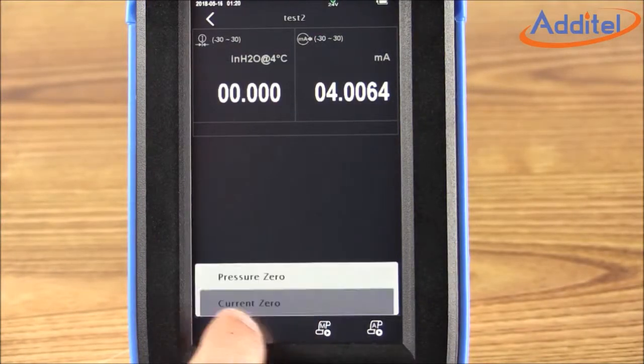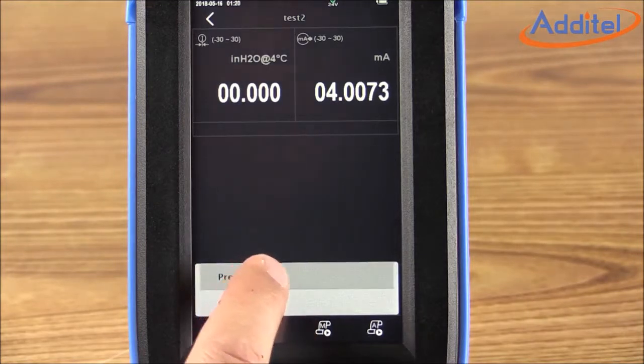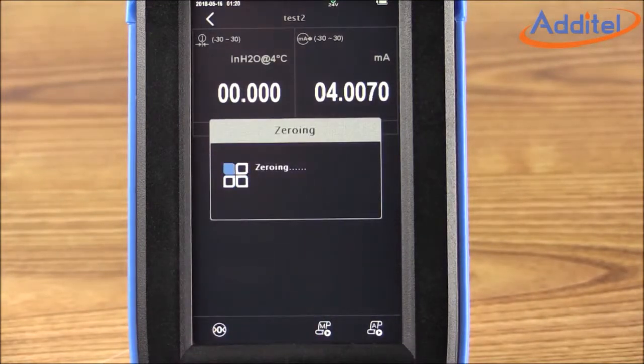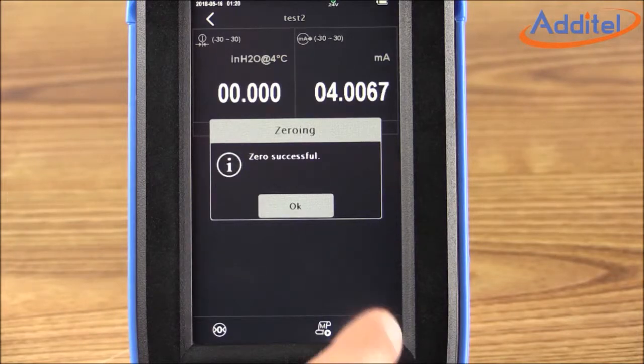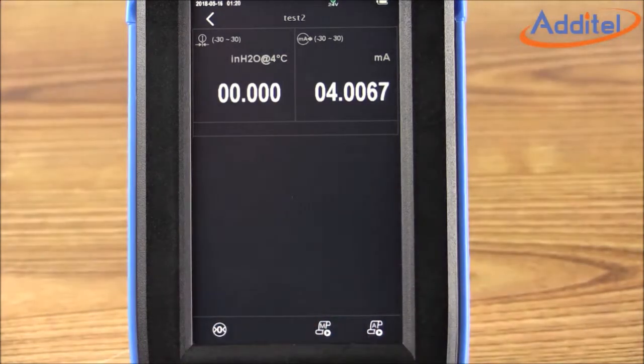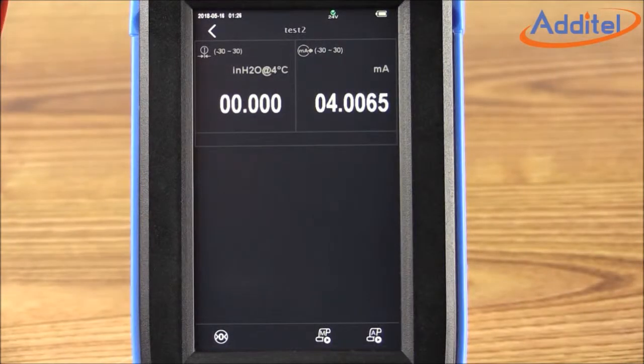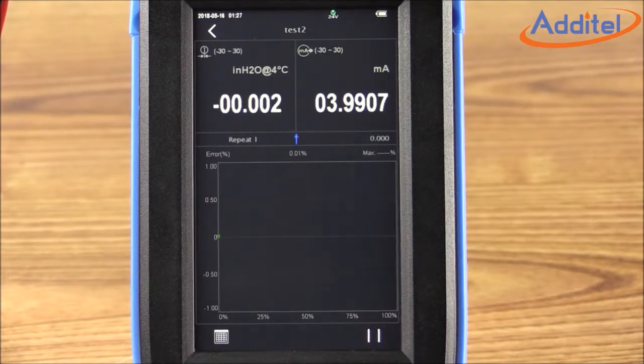To do so, click the icon in the lower left corner, and then click Pressure Zero. This will zero out the reference pressure for our calibration going forward. Shown in real time here, it only takes a few moments for the process to complete. Once done, click OK. Next, we have the option of either selecting a manual or automated cal. In this case, we'll select the automated cal in the lower right corner. The test will begin promptly.